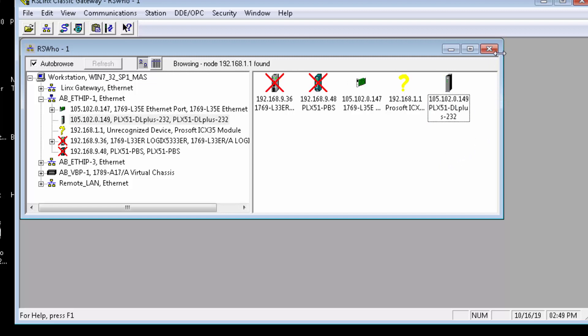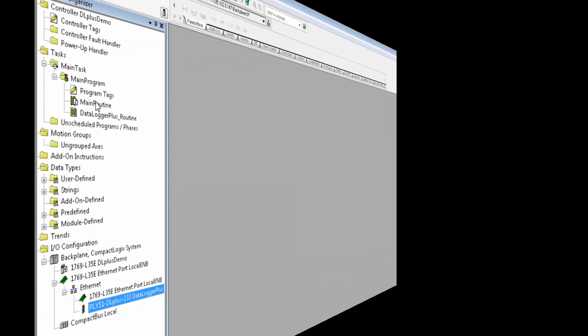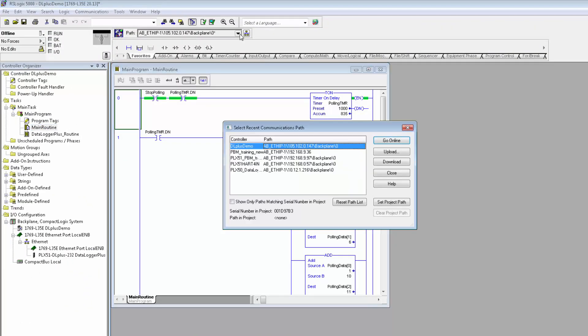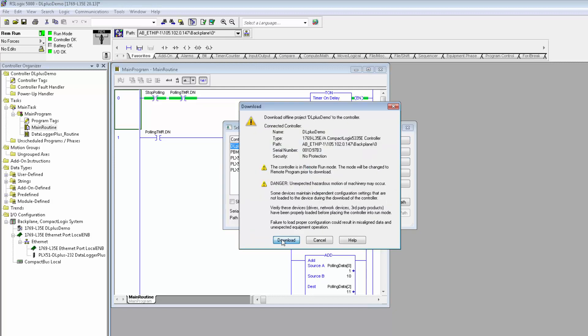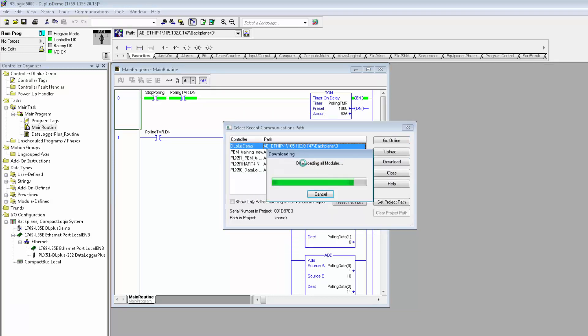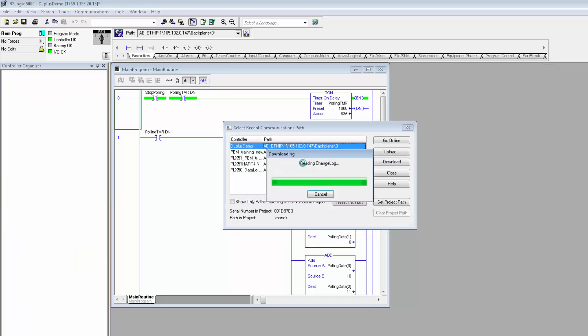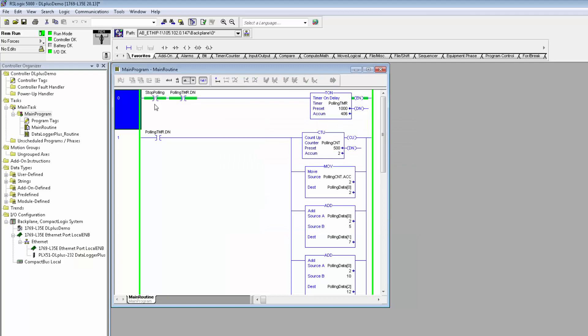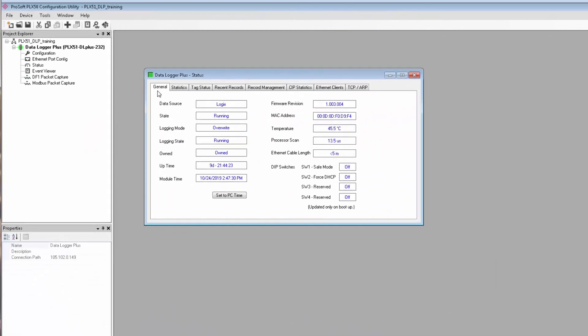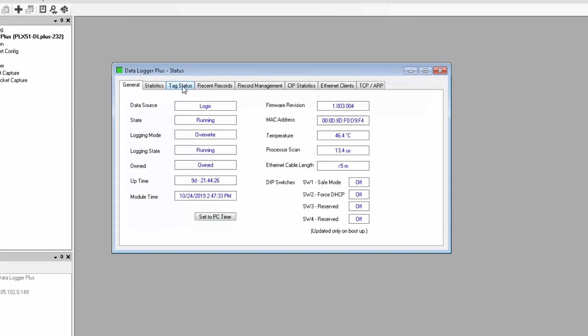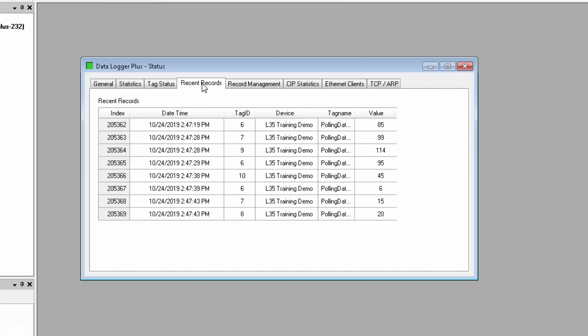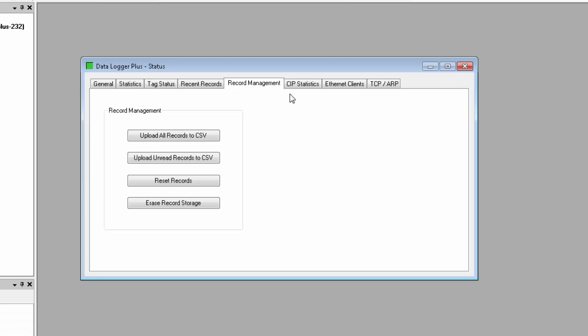We can now move into RS Logix, where I already have a project set up. I'll set my project to run mode, and the tags that I'm monitoring with the DataLogger Plus will begin incrementing through a range of values. I should be able to return to the configuration utility, open up the module status, and see that data is, in fact, being logged. The Tag Status tab will show a live stream of the data readings of your tags as they're being logged. The Recent Records tab shows a list of the last eight logs, and it will refresh as newer logs come in.